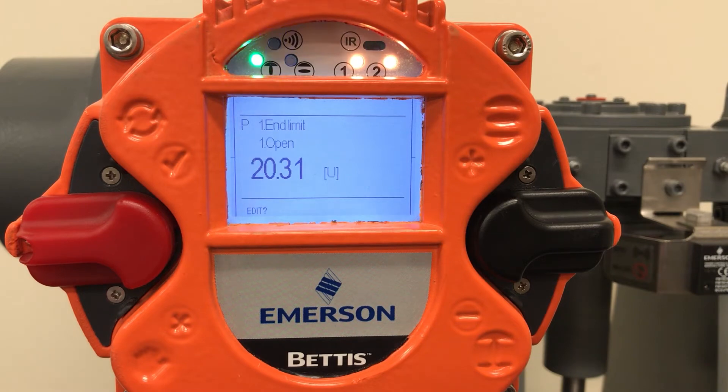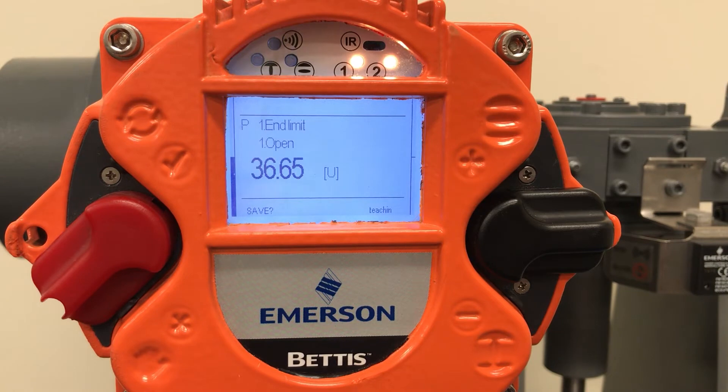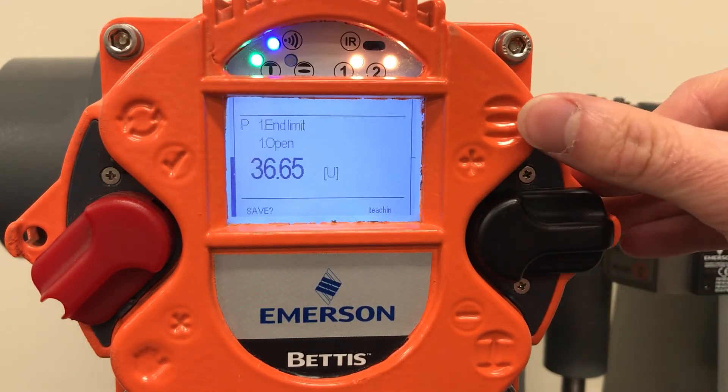To edit, flip the selector switch up. Now the text reads save with a question mark. Lock the red selector switch in local by pressing it down and you will see the word teach-in displayed in the bottom right hand corner. Use the black selector switch to run the actuator to the open position by pressing the switch up towards the open valve symbol.